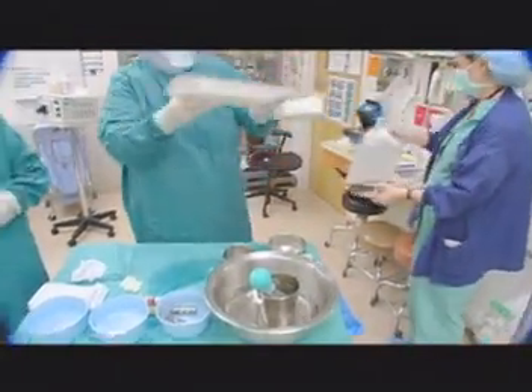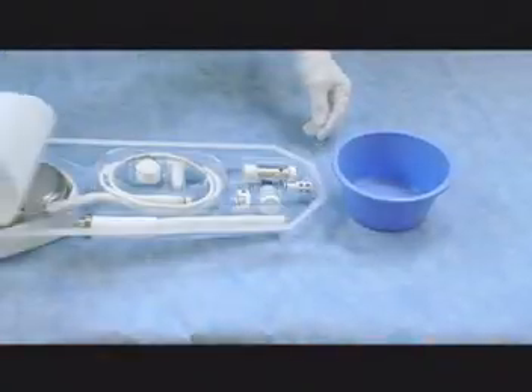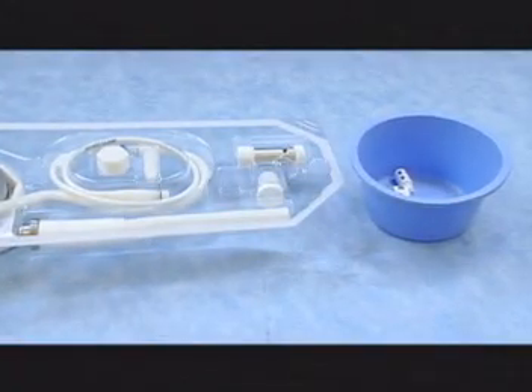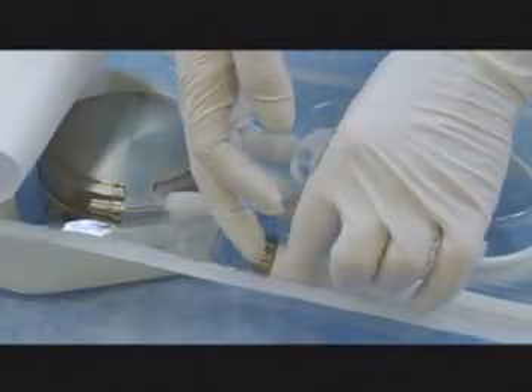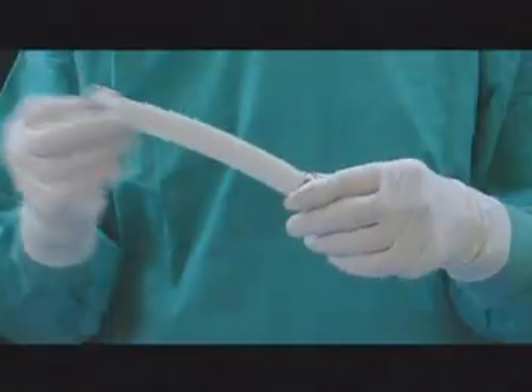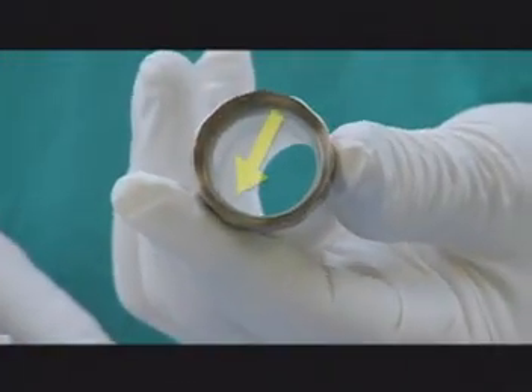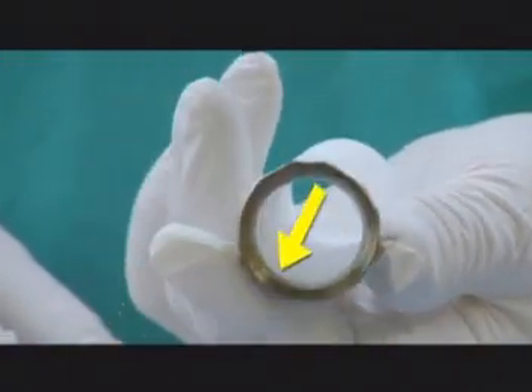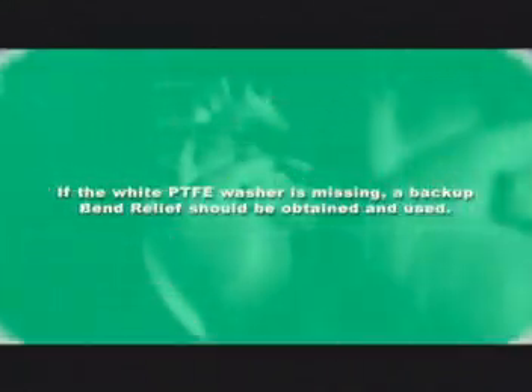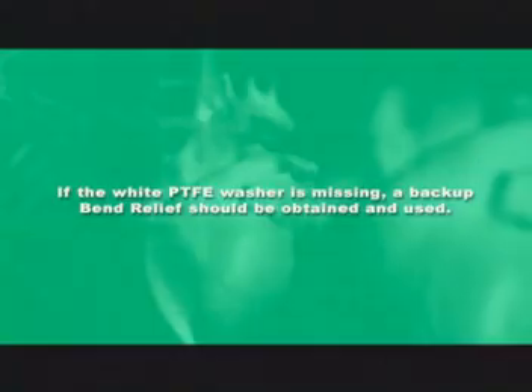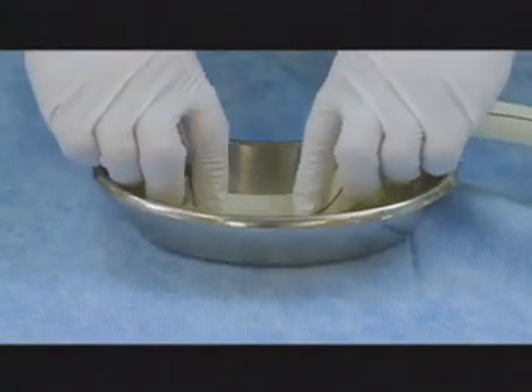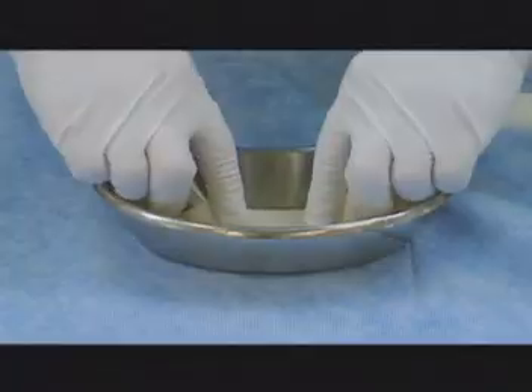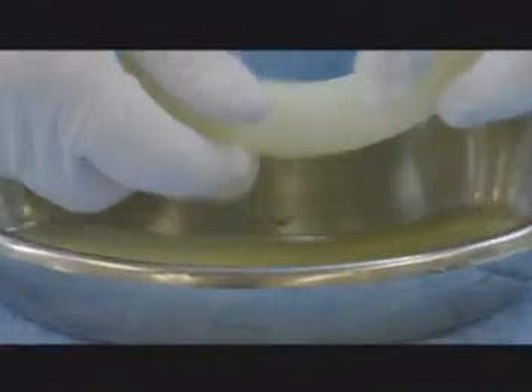Next, the sterile blister pouch that contains both the LVAD blood pump and several implant components should be opened by a sterile team member. Place the small implant components in a secure location on the sterile field. Now, remove the outflow graft bend relief from the outflow graft and inspect the screw ring of the bend relief. Verify the presence of its white PTFE washer. If it's missing, a backup bend relief should be obtained and used. In a sterile basin, coat the external surface of the outflow graft evenly with autologous serum or another approved pre-clotting agent.